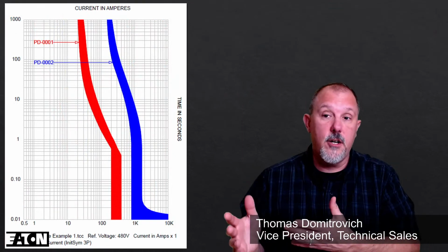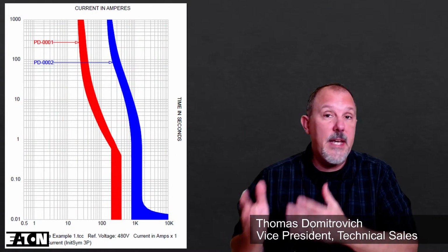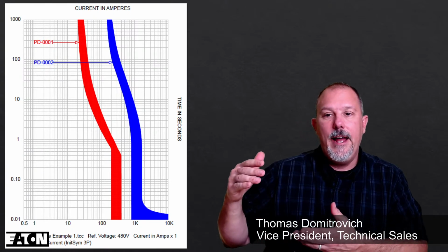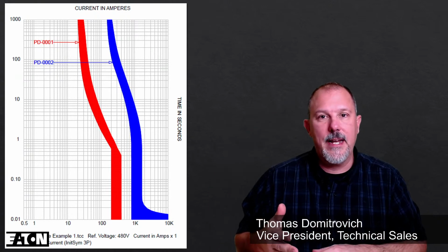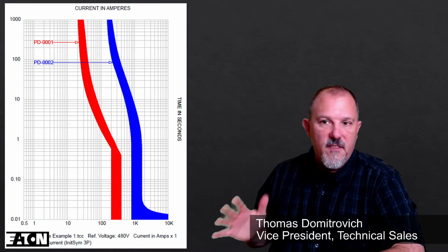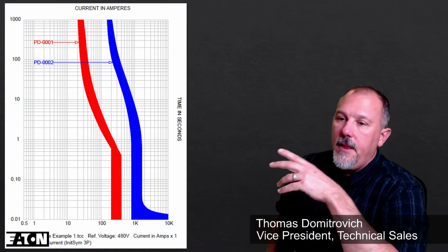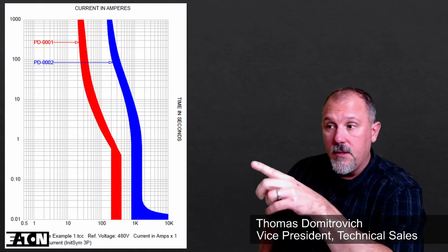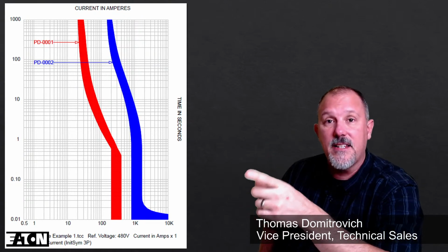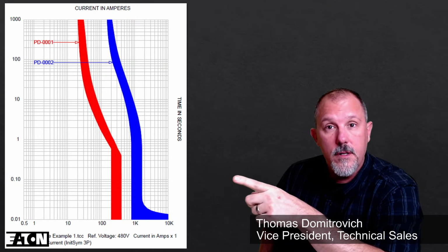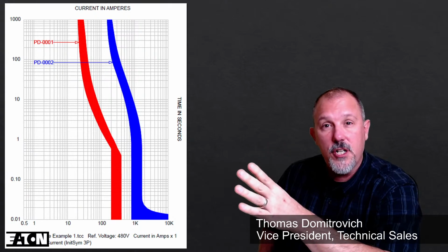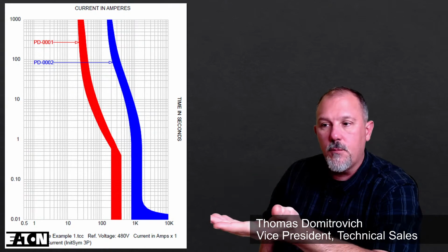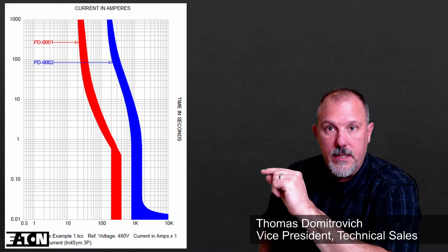Now, here's a set of curves, this is the BAB breaker, and you'll say, well, that's 0.01 seconds, and it goes all the way down to 0.01 seconds. That curve is not being cut off by fault currents. That curve does not begin to, the foot of that curve, like that red curve has a similar foot to the blue curve. But the red curve is just so fast when the fault currents get high enough that that circuit breaker opens faster than 0.01 seconds.